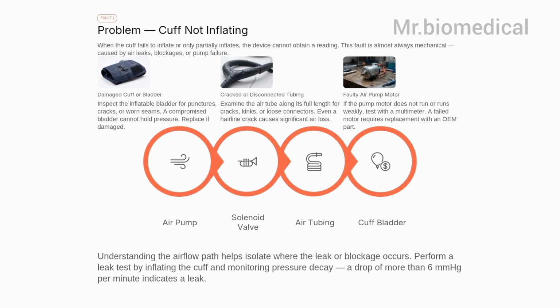Air starts from where? Pump. Moves through the tubing, passes the valve, and finally reaches the cuff. If any component here leaks, pressure will not build up. Okay, that's why the cuff is not inflating. As a service engineer, first we have to inspect the cuff bladder. Then we have to see the air tubing, connectors, and air pump motor. Here's a practical question. If the cuff is inflated to 180 mmHg and after 1 minute it drops significantly, what does it indicate? Means there is some leak. A useful trick is to bend the tubing and inspect carefully because tiny cracks may not be visible. Always troubleshoot systematically from the pump to the cuff instead of randomly replacing the parts.